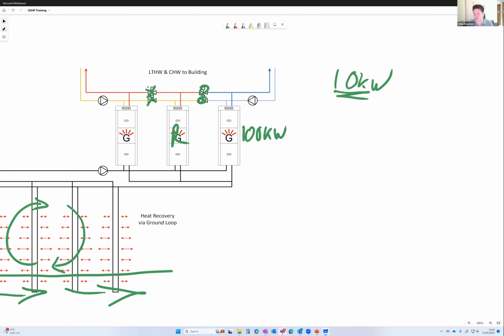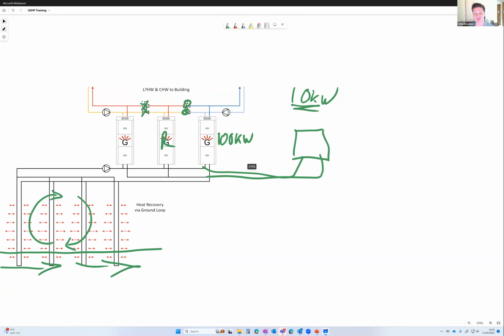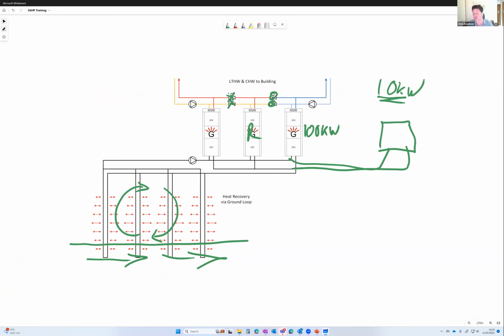So that's going to result in a few things. It's going to be high wear condition for the heat pump. It's like reversing and forwarding your car repeatedly. And it's also going to mean you're going to get a lot of starts and stops, which again is bad for longevity on that heat pump. So it's going to be inefficient and it's going to cause heat pump failures. So in that instance, what you'd probably be better to do is just get a little 10 kilowatt heat pump and connect it up to the ground loop and dedicate it to that cooling load. So that's some of the practical considerations for how you actually put ground source into a commercial building.